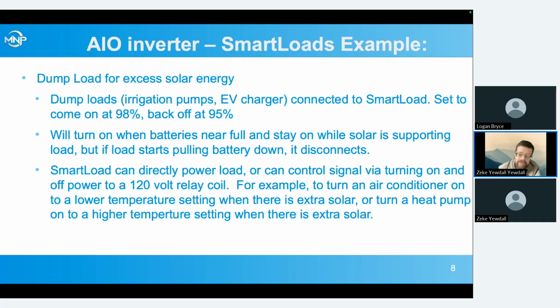We can directly power the load off the smart load, or we can take one leg of the smart load and use it to power the 120-volt coil of a relay, and then we can use that relay to connect to other things. For example, we can connect into a thermostat system, and maybe when we've got excess solar, we turn our air conditioner higher, or maybe we drop it down to 65 degrees and really overcool that space because we've got extra solar, and we'd rather do that than dumping that solar and then having to draw from the batteries later in the evening.